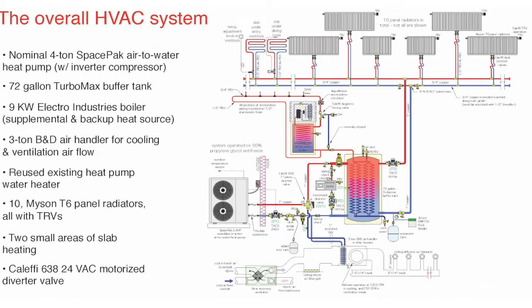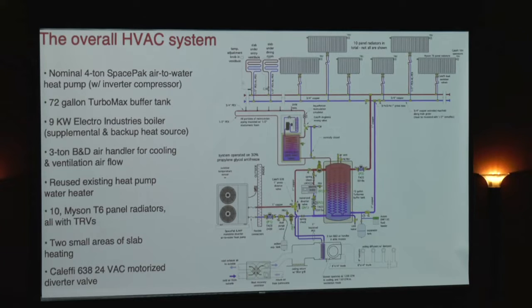So I believe right now, I'd have to check the current settings, but let's say we had it set for first stage at 100 degrees. If it drops another 5 degrees, because the heat pump isn't keeping up, we'll bring on the electric boiler. We actually used the electric boiler for about a month just to provide heat during construction before we had the heat pump connected, and it worked fine.